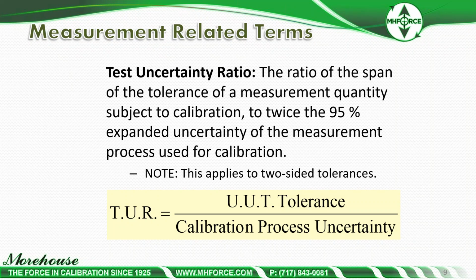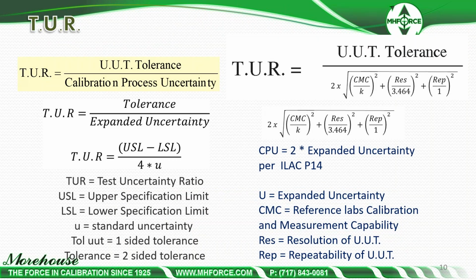A lot of people look at test uncertainty ratio. That's the ratio of span of tolerance of the measurement quantity subject to calibration to twice the 95% expanded uncertainty of the measurement process used for the calibration. This is found from ANSI Z540. It's a UUT tolerance divided by the calibration process uncertainty. We've seen it listed out this way. Different specifications, tolerance by the expanded uncertainty. We've also seen the upper specification minus the lower, divided by 4 times U.